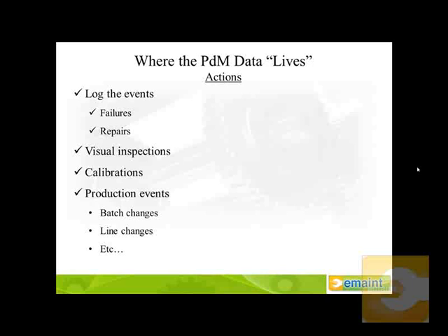What this adds for us is the capability of being able to highlight what those repairs are, so that we're not just sending our craft out in the aspect of, okay, we have an issue out here, we know that it's a vibration because the operator can feel it on his feet when he's walking past it. Let's go find out what the problem is. What we're doing is we're taking and capturing that data through the use of PdM technologies. We're putting that PdM data into our CMMS system. We're analyzing it and being able to determine when and where that work needs to be done.